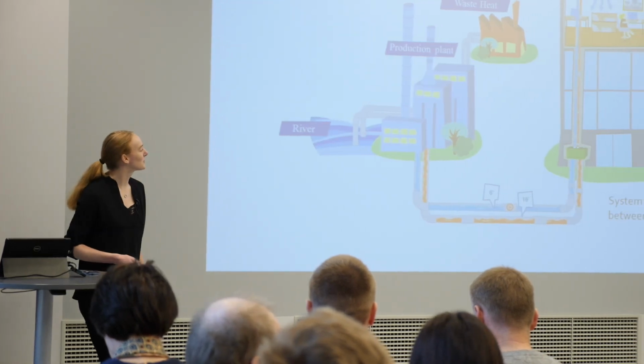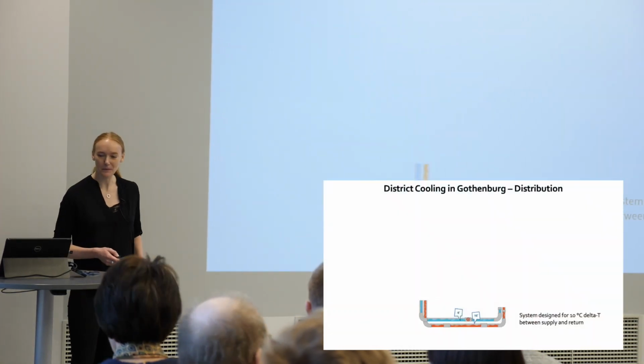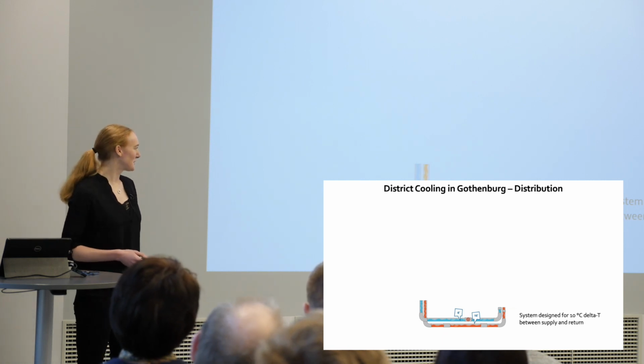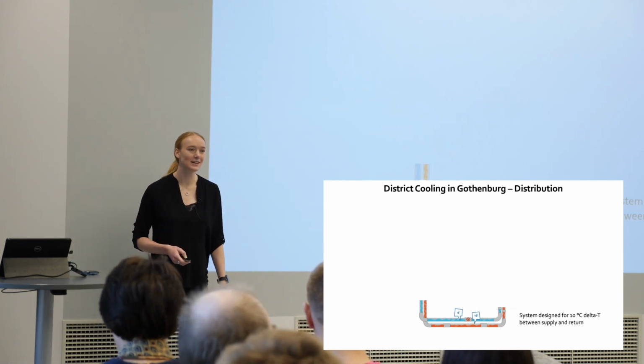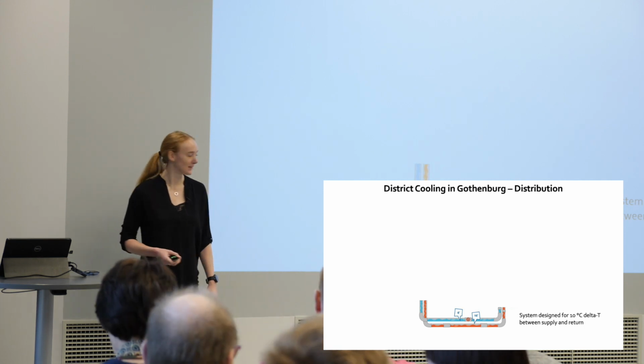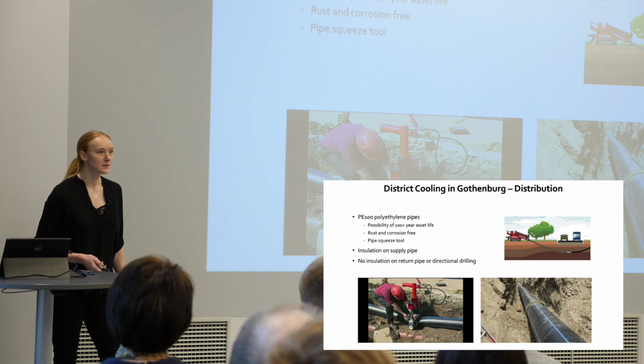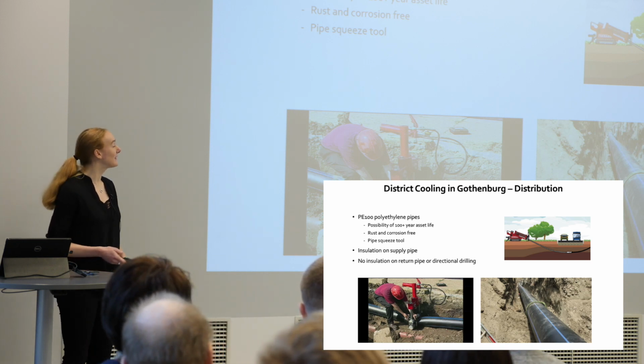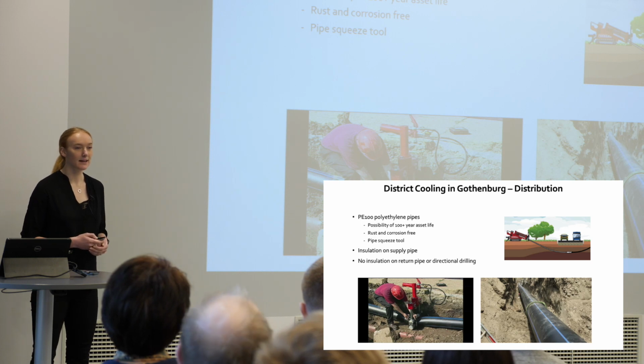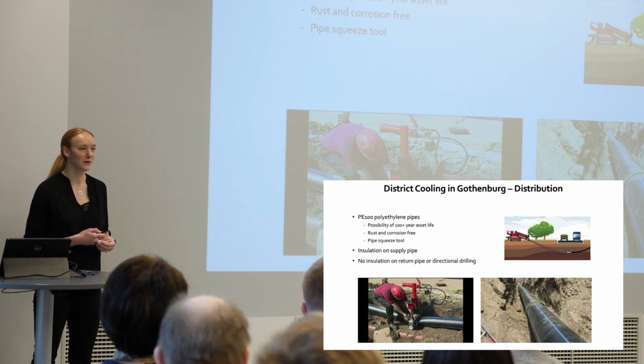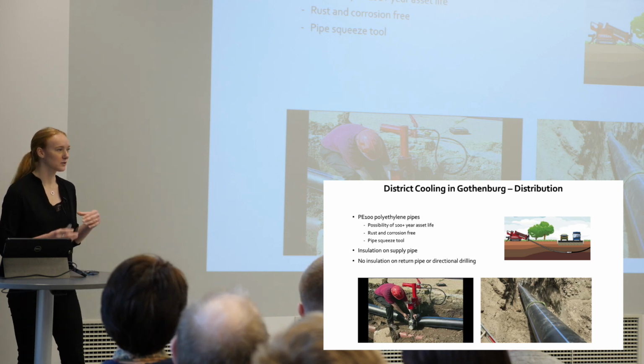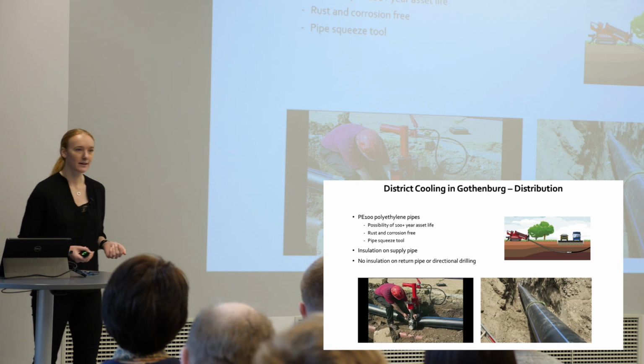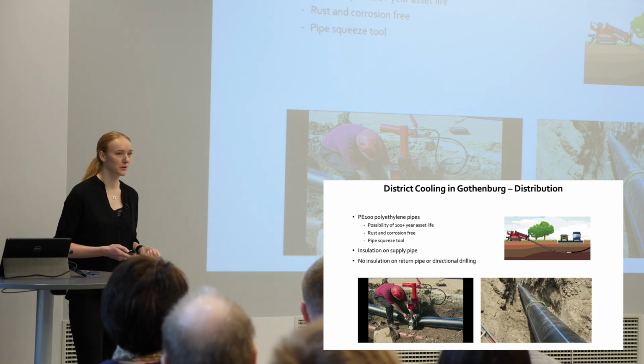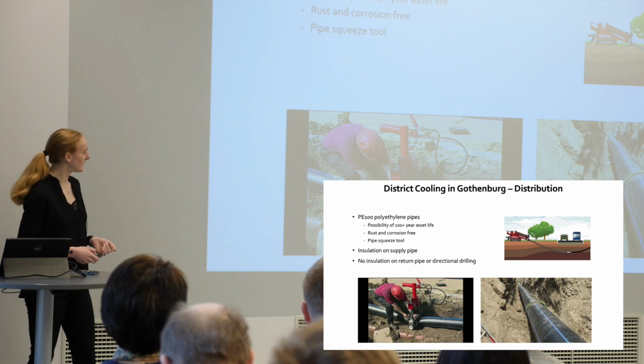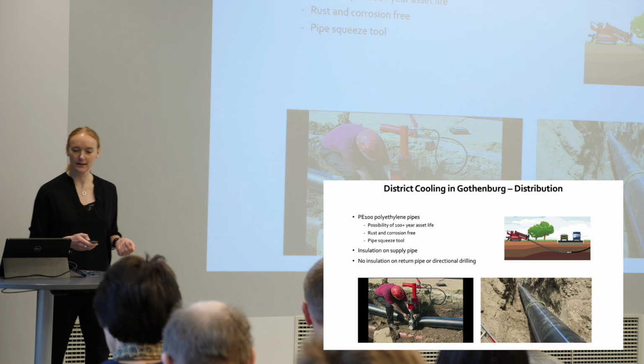And then we move on to the distribution system. The distribution system has been designed for a supply temperature of 6 degrees and a return temperature of 16, so that gives a delta T of 10 degrees. The pipes used are PE 100 polyethylene pipes, and they have a very long asset life, possibly more than 100 years. Compared to steel, they're completely rust and corrosion free, and also quite easy to install, because you can use this handy little squeeze tool and easily cut them where needed.